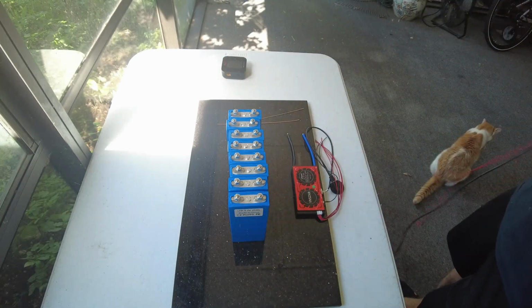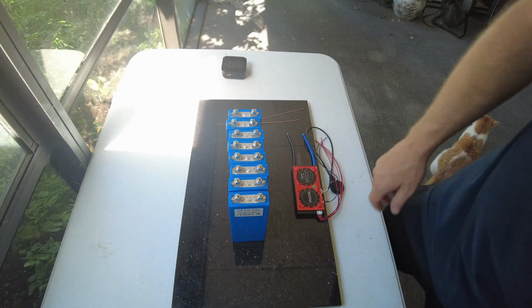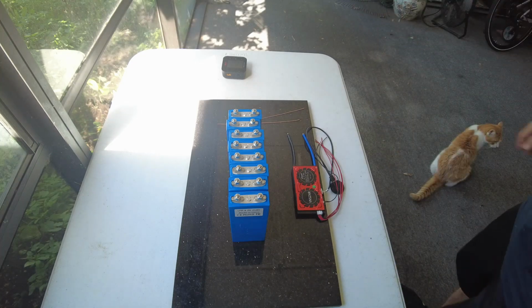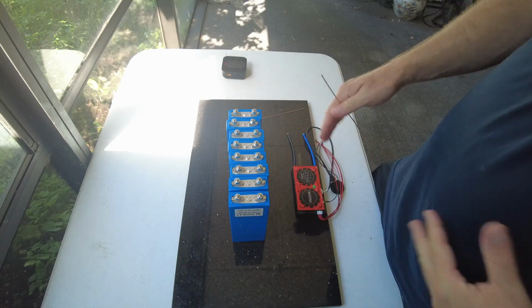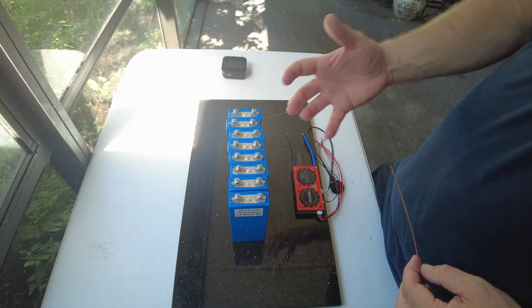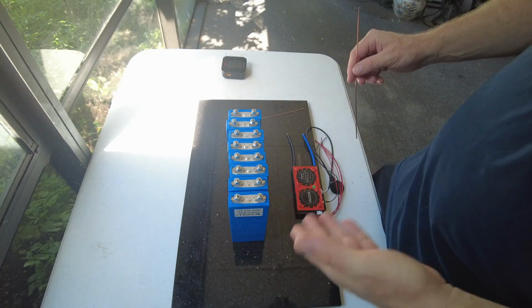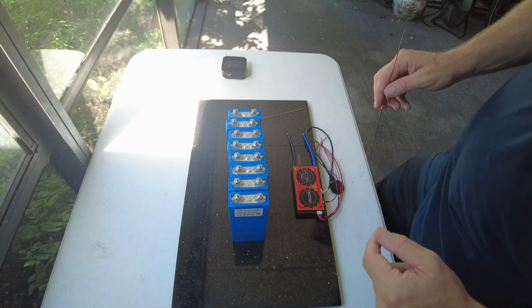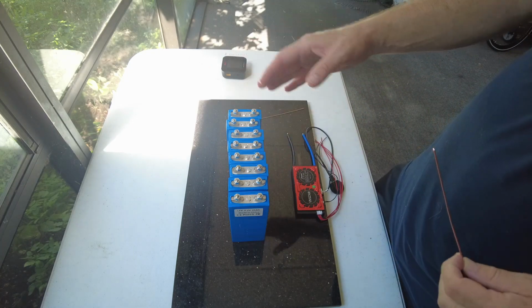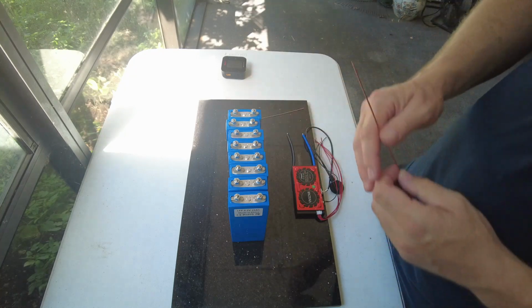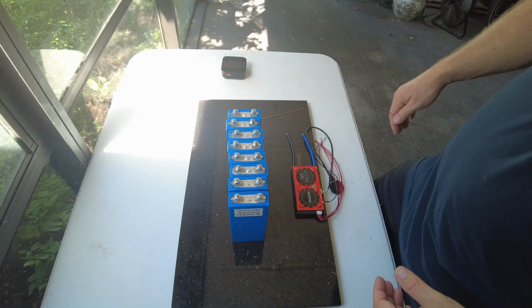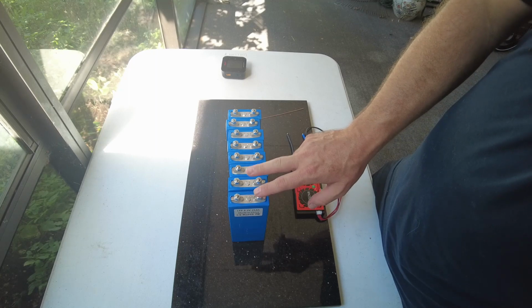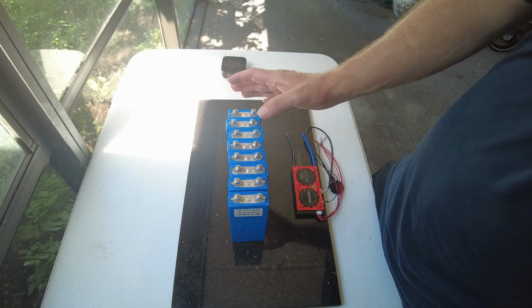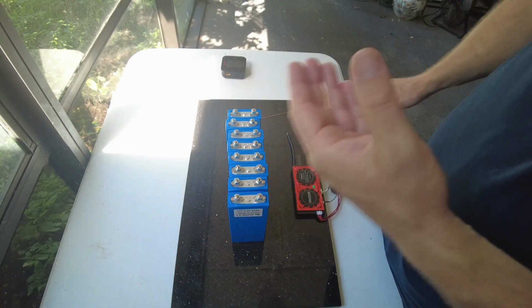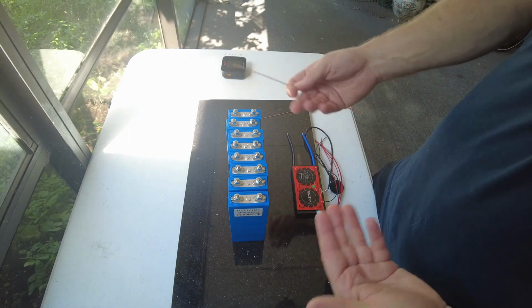Yep, so we're good. Now some of you are going to go, well, they're all the same voltage, so they're balanced. Nope, they're not, because with lithium iron phosphate, the voltage does not tell you a whole lot about the state of charge. The low end of the voltage, like 2.5 or 2.7, will basically tell you it's pretty much drained to 0. And the high end, like 3.4 to 3.65, will pretty much tell you they're fully charged. But anything in between, it's anybody's guess. You literally could have 2 cells that say 3.2 volts but be like 50% different in state of charge from one another. So that middle voltage range doesn't tell you which one has more charge. It doesn't.